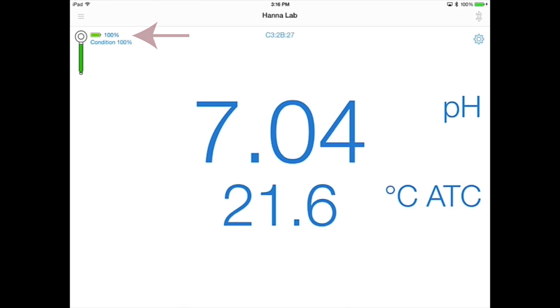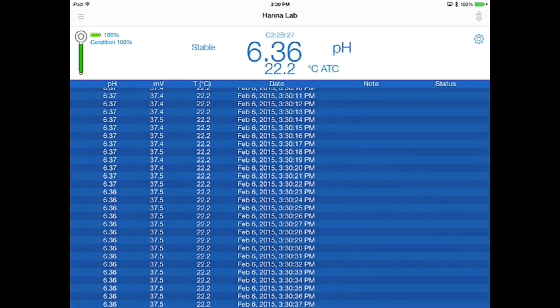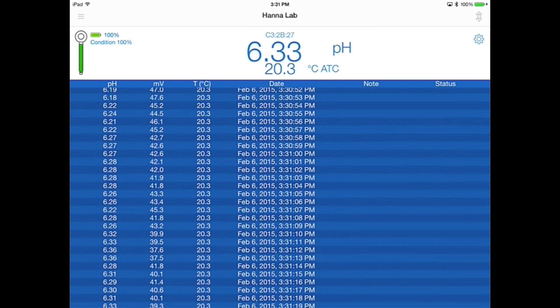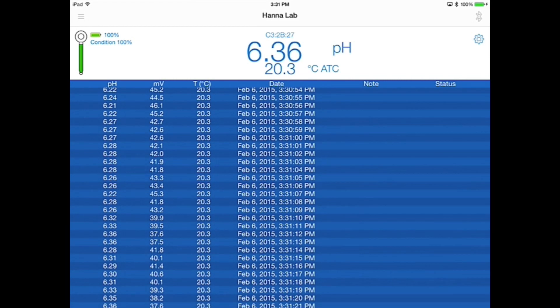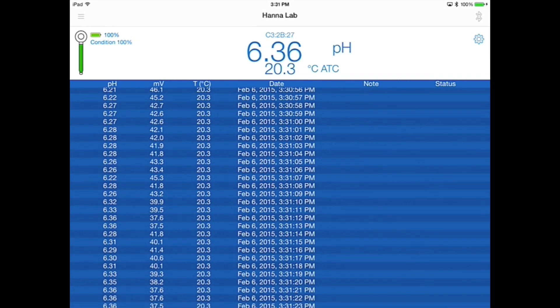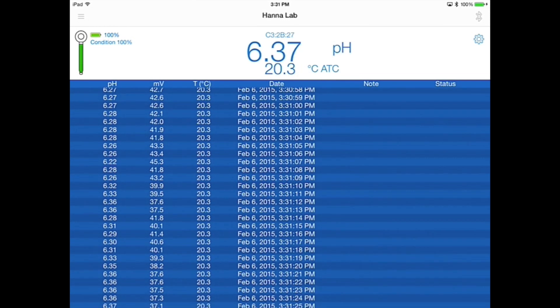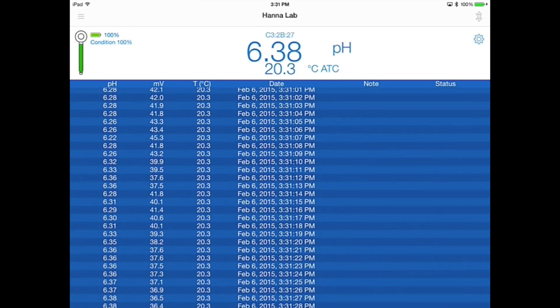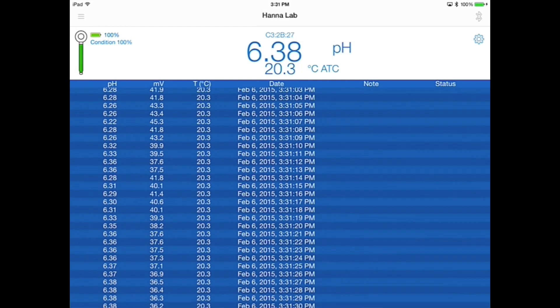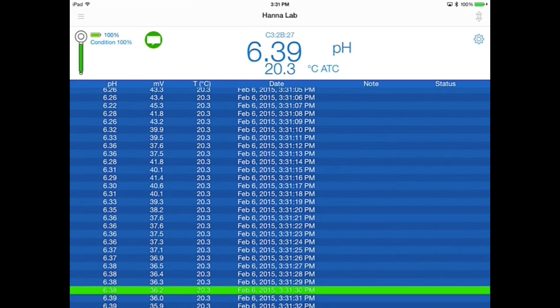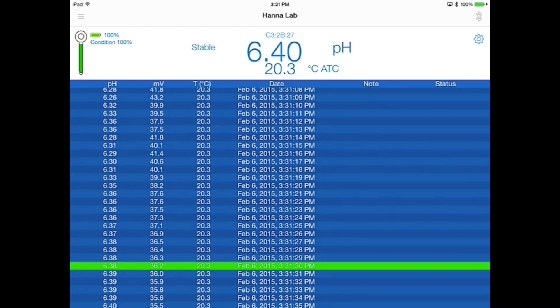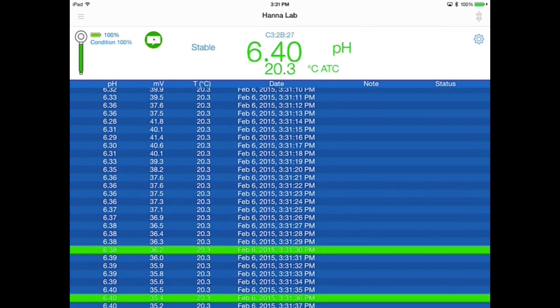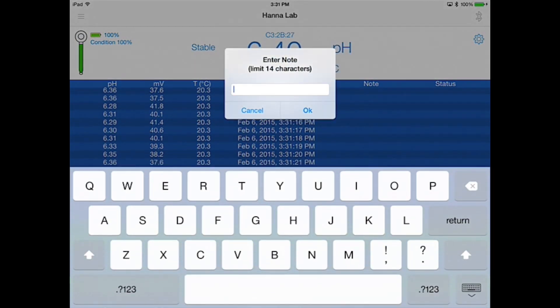The data logging feature is always active and will log a parameter, pH, and temperature measurement every second as soon as the probe is detected. Readings are automatically saved to a history file every hour the probe is connected to the app. The current reading may be tagged or annotated by tapping the probe icon in the top left corner of the iPad display. A short note can be added to the annotated reading by tapping the message icon immediately after tagging the reading.